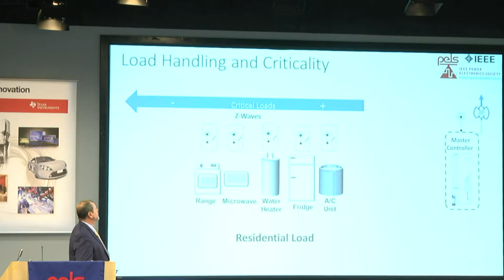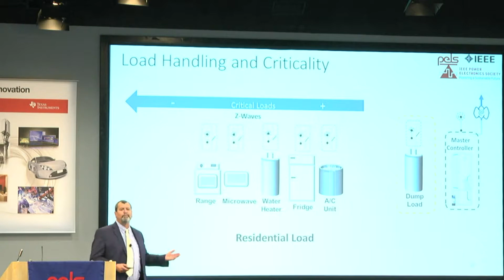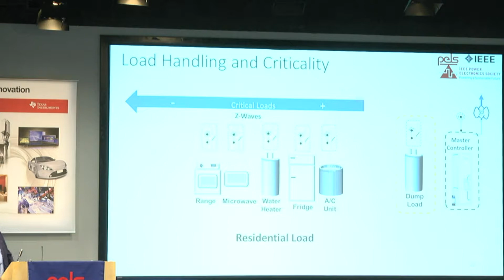The droop control becomes way more complex than people have been talking about. In addition, you have to evaluate the loads — why you don't care about them in a specific moment. Maybe you don't care about the TV, or about running washers and dryers sometimes, or about lighting depending on whether it's daytime. And when you are generating too much power that you cannot dump into your batteries anymore because your storage is full, you need to dump the energy, because remember, power in has to be equal to power out. If not, you lose the system.